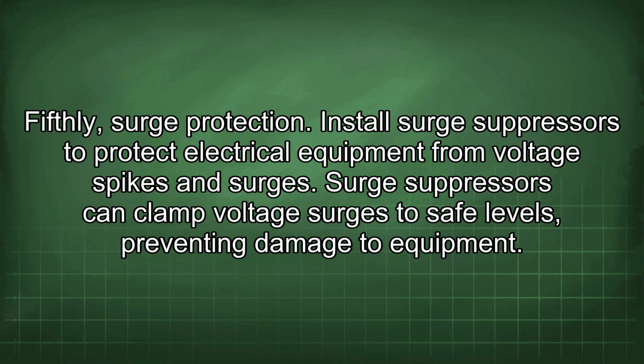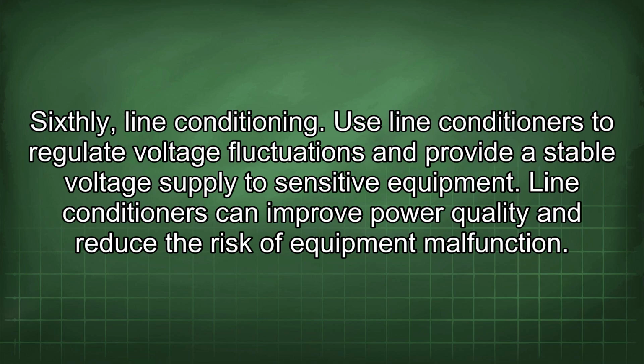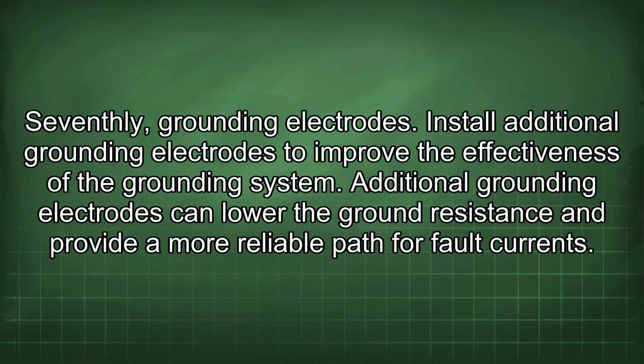Fifthly, surge protection. Install surge suppressors to protect electrical equipment from voltage spikes and surges. Surge suppressors can clamp voltage surges to safe levels, preventing damage to equipment. Sixthly, line conditioning. Use line conditioners to regulate voltage fluctuations and provide a stable voltage supply to sensitive equipment. Line conditioners can improve power quality and reduce the risk of equipment malfunction. Seventhly, grounding electrodes. Install additional grounding electrodes to improve the effectiveness of the grounding system. Additional grounding electrodes can lower the ground resistance and provide a more reliable path for fault currents.